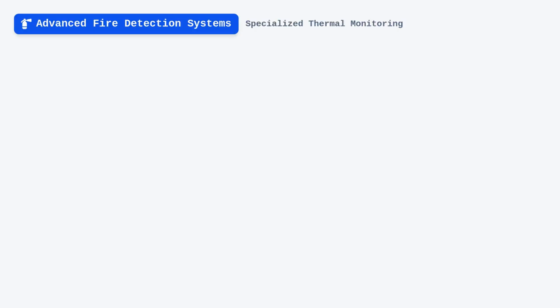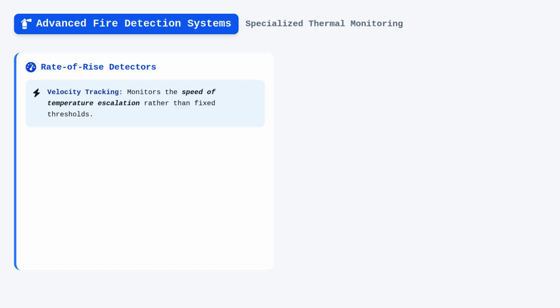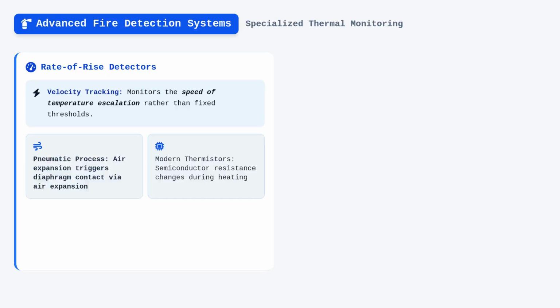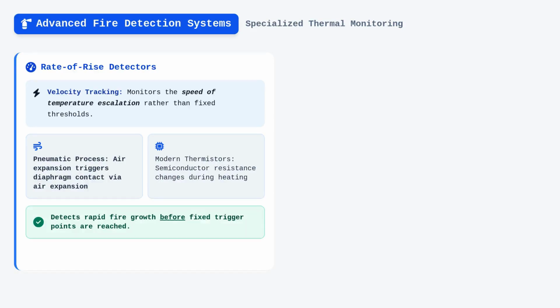Moving into more sophisticated diagnostic territory, we must consider the rate of rise technology, which monitors the velocity of temperature escalation rather than just the absolute temperature. These detectors typically utilize pneumatic principles, where air trapped in a chamber expands as it heats, causing a diaphragm to depress electrical contacts. Modern iterations employ thermistors, which are semiconductors that demonstrate a sharp change in electrical resistance as they heat up. The advantage here is the ability to detect a rapid fire development even before the ambient temperature reaches a fixed temperature trigger point.